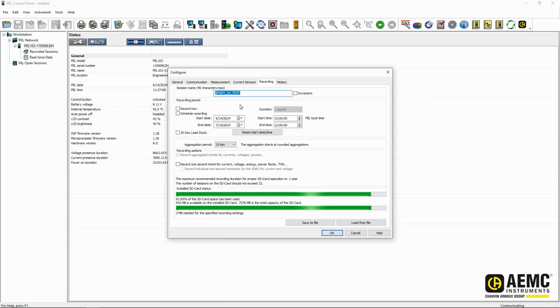Here we can set a session name, which will become the file name of the recording. Next, we can select the recording period and schedule. We will schedule our recording to start and stop at specific times if that's applicable to your recording project. This can be helpful to control the amount of data that is produced, or if you're using the PEL to capture usage or monitor voltage levels during specific times of the day.